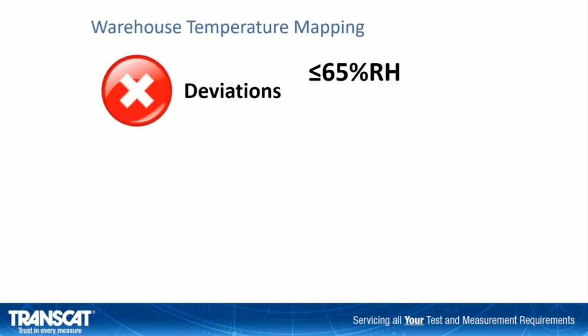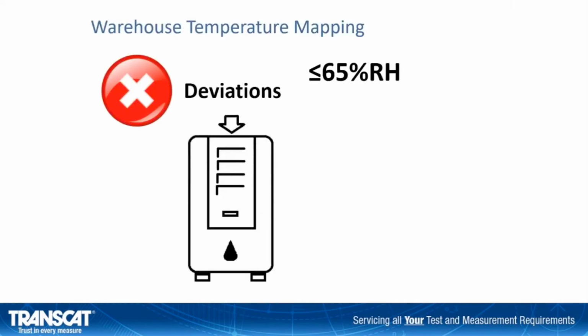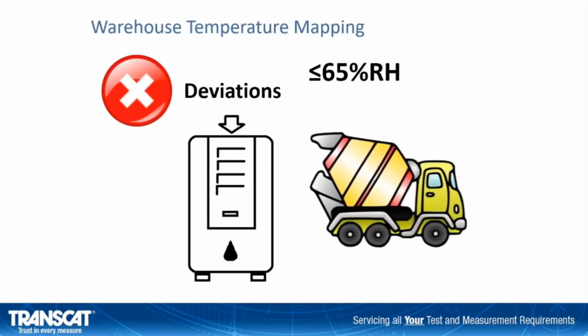Sometimes excursions are from data that exceeds the humidity specification limit. This can be resolved by adding a commercial-grade dehumidifier or humidity control to the HVAC system. We've also observed excessive humidity excursions caused by the curing of freshly poured foundation, which can take months to cure under certain conditions.